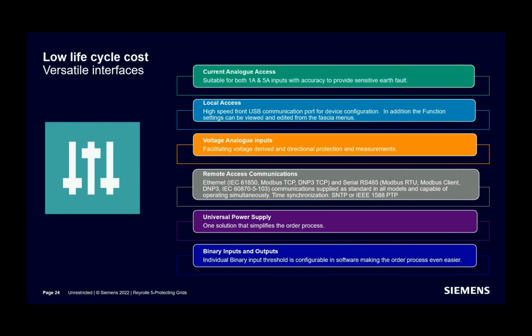And all binary input thresholds are configurable inside the software individually. So you can choose binary input 1 to operate as a 24 volt DC input, and you can choose binary input 10 to operate as 110 volt DC input individually, and all the circuits are completely independent. There are no commons. So electrically and software-wise, everything is isolated.